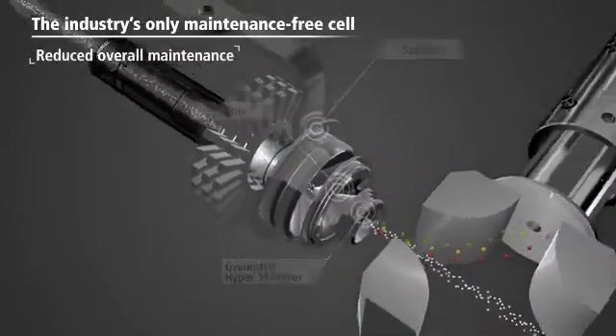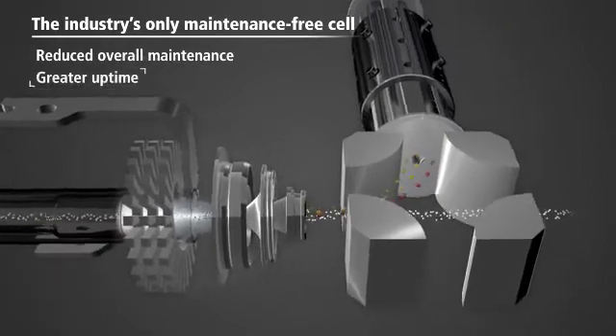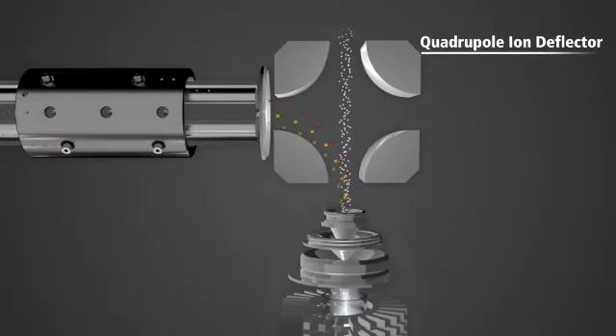It's the only ICP-MS with a cell that never needs replacement, so you'll spend more time running samples and less time on maintenance. Bending the beam 90 degrees, the quadrupole ion deflector is one of three quadrupoles in the instrument. Ions of a specific mass range are passed into the next quadrupole while simultaneously filtering off neutrals and other unwanted material.